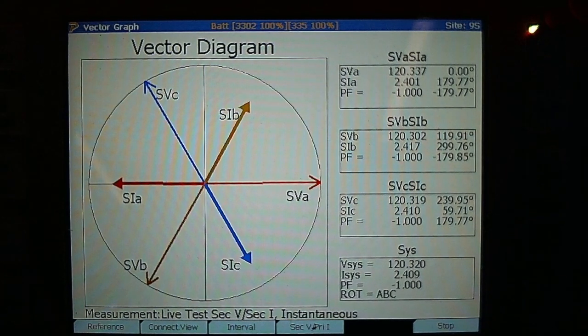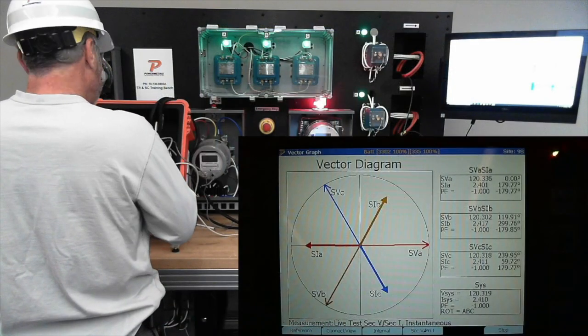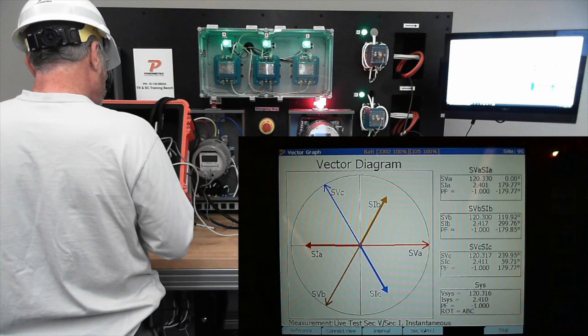But let's just say if we were just looking at this, what could be some other things that could cause this? I literally could have had a contractor out there wiring them wrong, incorrectly, on all three phases at this site on the CTs, right? So it'd give me polarity reversal on all three phases. Doesn't happen a lot, but don't tell me it hasn't happened, because I know it has. So that could be another reason that everyone, all three phases, are 180 degrees out. That'll show polarity reversal on them, right?